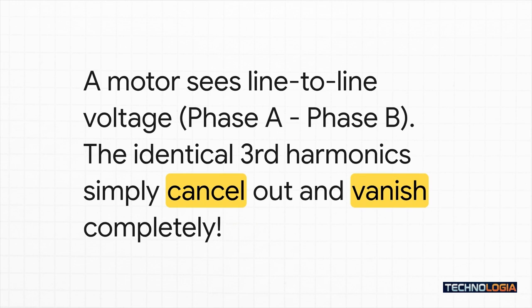A three-phase motor doesn't actually feel the voltage on any single wire. What it feels is the difference in voltage between the wires, what's called the line-to-line voltage. So when the motor looks at the difference between phase A and phase B, those two identical third harmonic distortions get subtracted from each other, and poof, they completely disappear. They were just a ghost in the machine, a tool you use to get more headroom for the real wave that the motor actually feels.